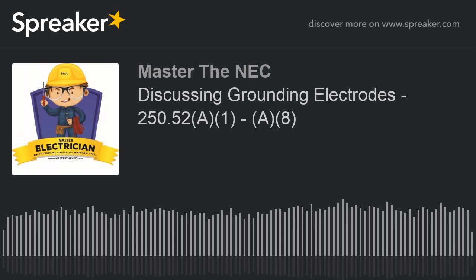Also, remember, if I'm going from one grounding electrode conductor to a ground rod, and I plan on jumping from that ground rod over to, let's say, a concrete-encased electrode, and I want to kind of loop these, you can't do that. In other words, there used to be a term called the sole connection, and that's been removed from the NEC for clarity.